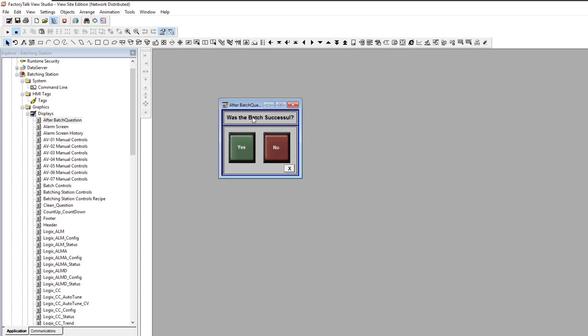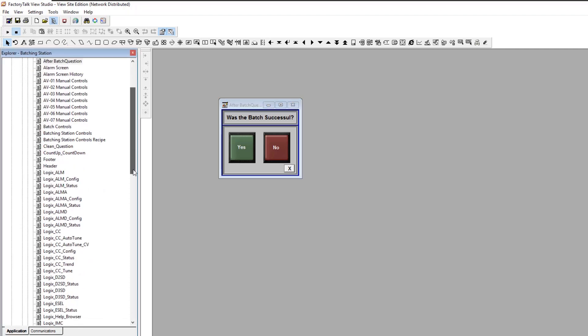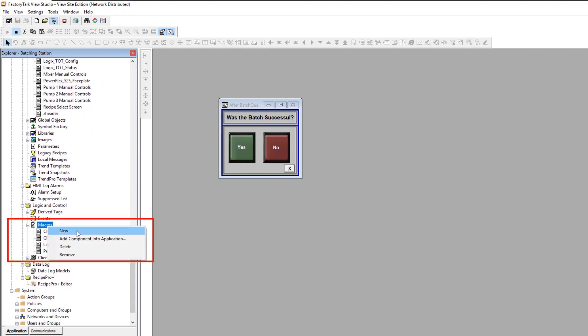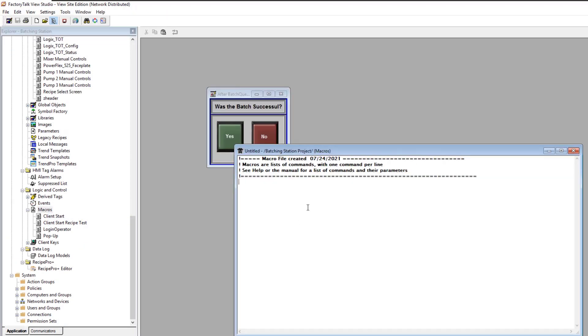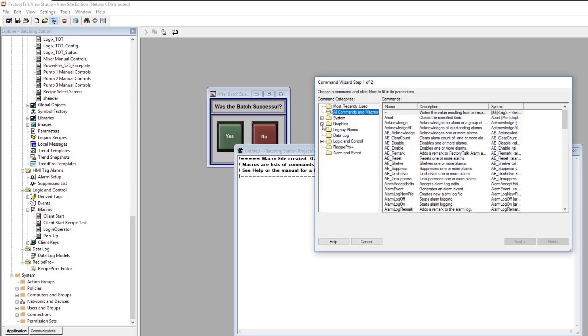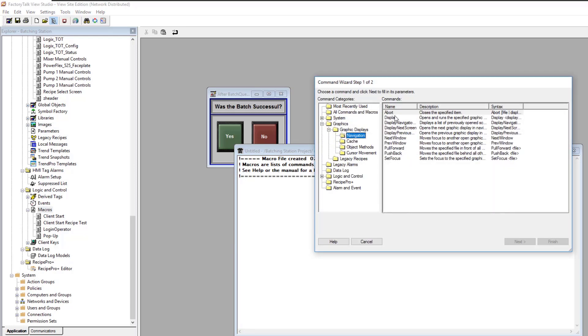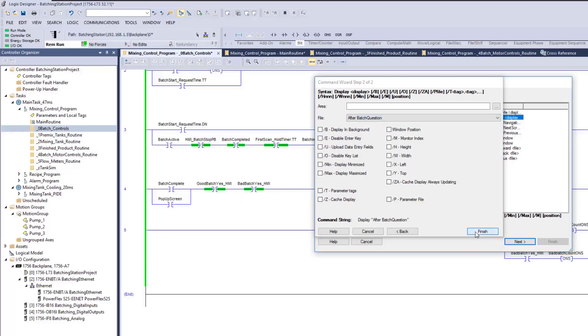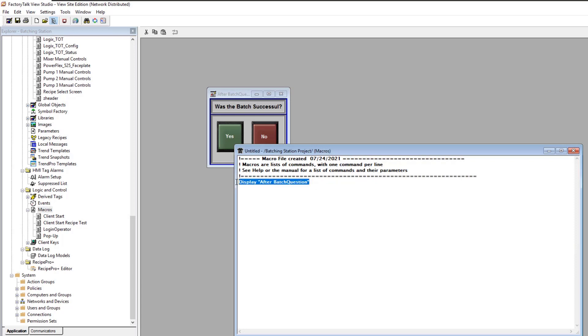So what we're going to do — I've already made this screen to save us some time — we're going to show you how to do this. First, if we want to pop up this screen, we need to understand a couple of things. We need to have a macro. I'm going to make a macro right here and call it a new macro, and we're going to say display. Instead of just typing it, you can double-click and come over here to display, navigation, display, and then pick your display. This is going to be the screen I made — it's called 'after batch question.' Then I just hit finish, and that's all I have to do on that macro.